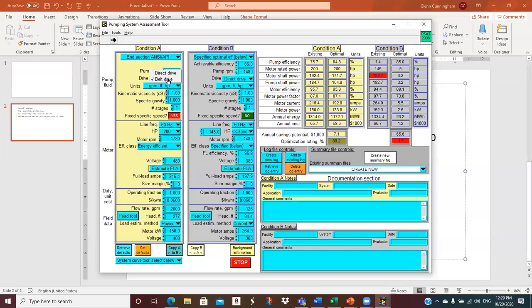So if we say, nah, we don't have belts, we're just playing around, then the power that comes out of the motor goes directly into the pump. So they're the same thing, which is appropriate. Motor efficiency. Oh, power factor. That's interesting. And then it shows you a motor current. So it takes this power measurement and backs out what the motor current would be and shows you that. That's the power. It just repeats. You told it you measured 150 kW and it believes you. It will believe you every time, whether you get it right or not.